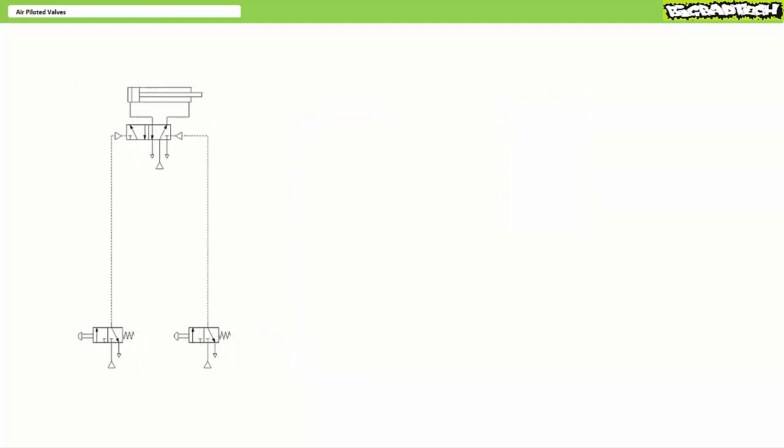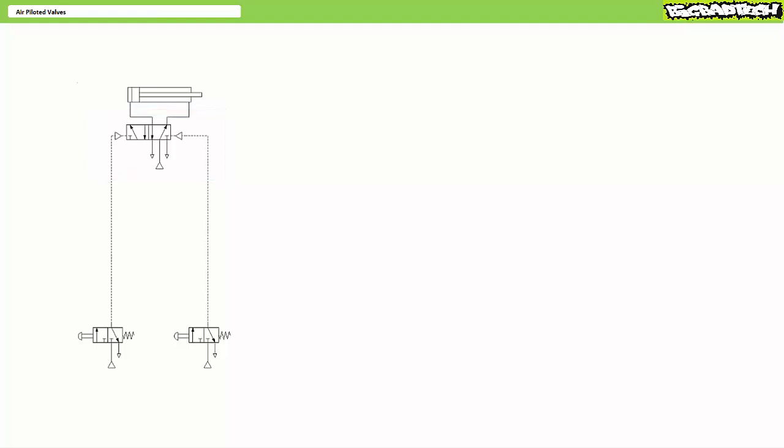One means of correcting this flaw is with the use of a double air piloted five by two directional control valve indirectly controlled by two normally closed push button operated three by two directional control valves, still the requisite distance from the actuator.